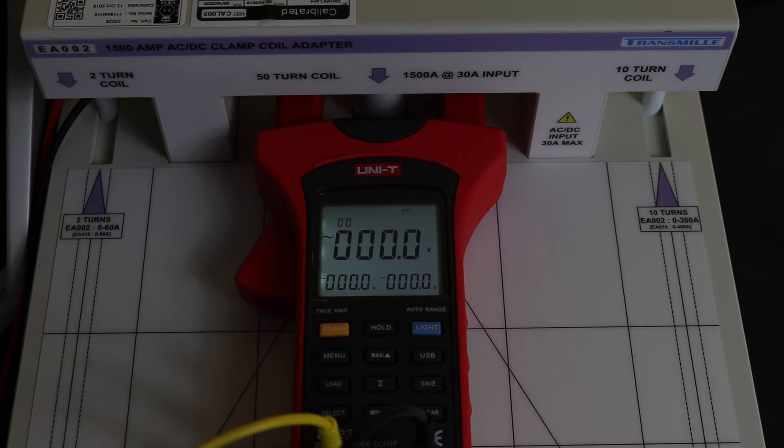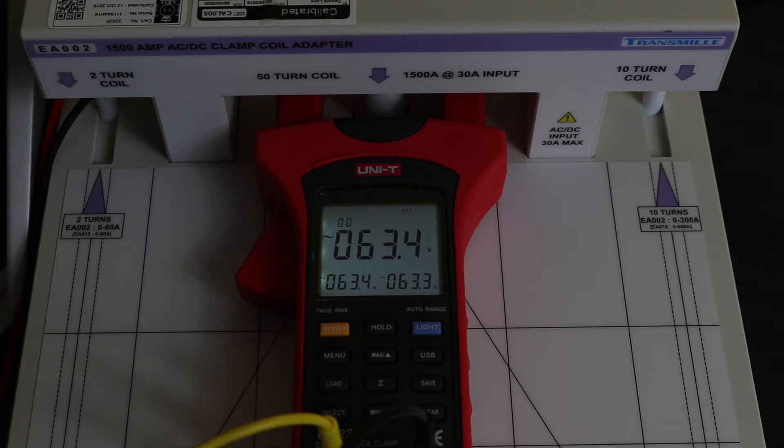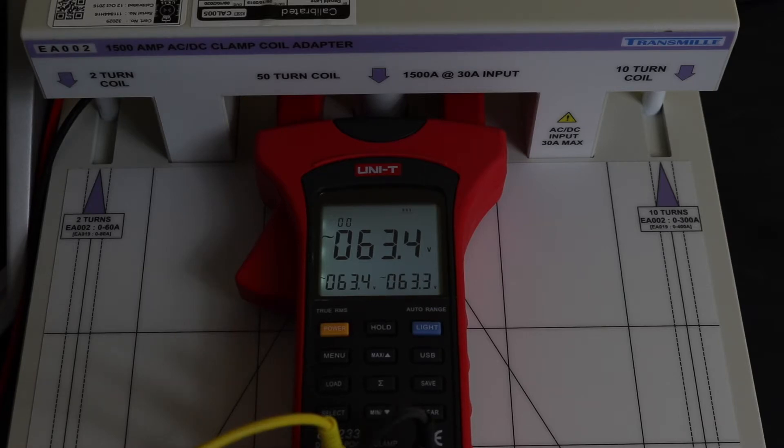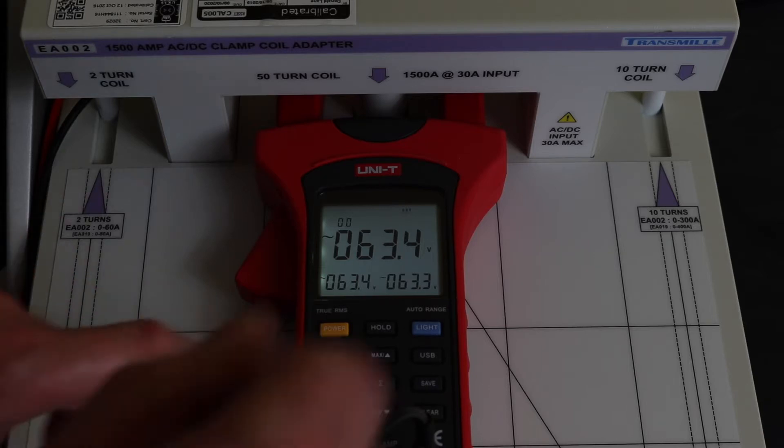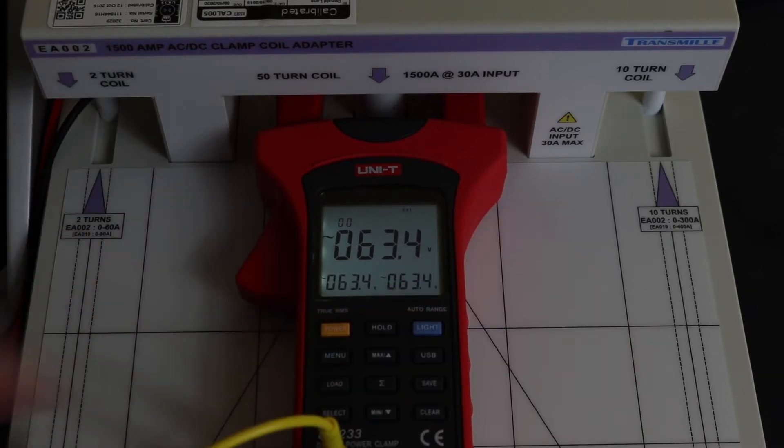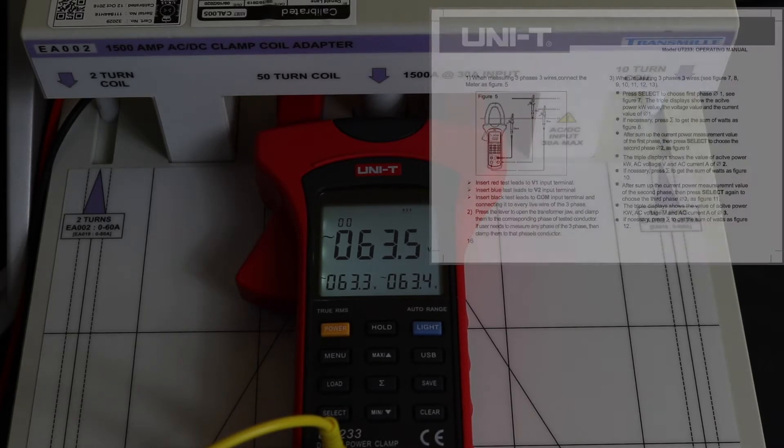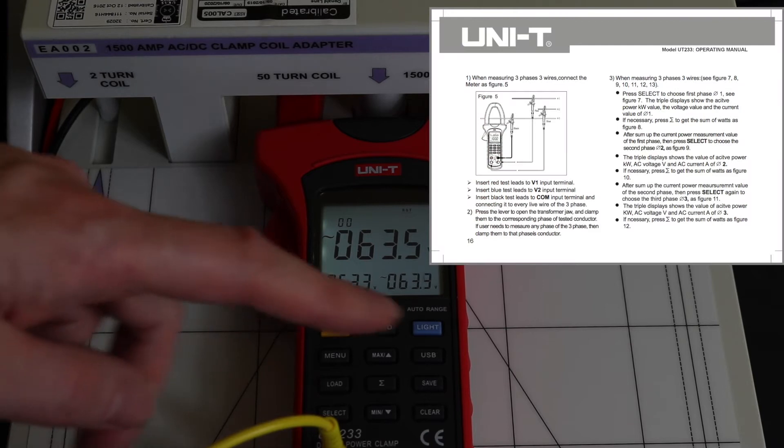A couple of anomalies I've noticed while using the instrument. You can see here I am set up in three-phase voltage measurement and I've got all three phases at 63.5V, which is 110 volts between phases, and I'm displaying the live to neutral voltage. Take the neutral out - that still works.